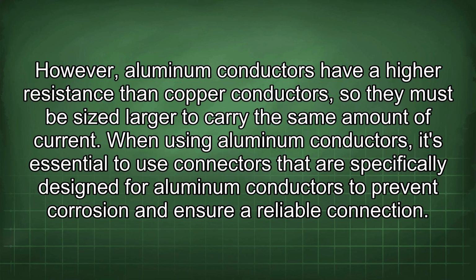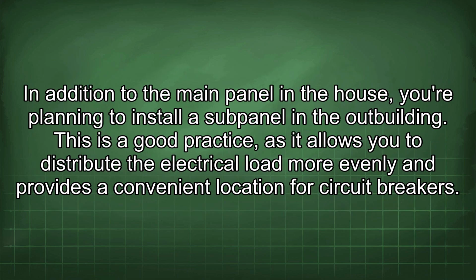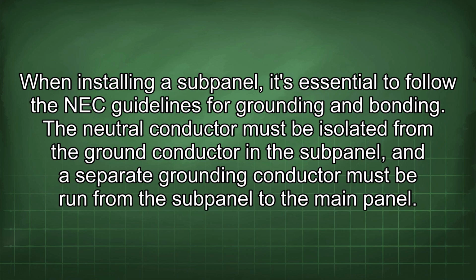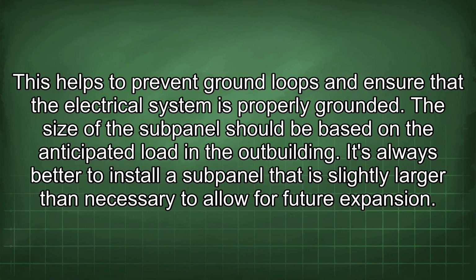In addition to the main panel in the house, you're planning to install a subpanel in the outbuilding. This is a good practice, as it allows you to distribute the electrical load more evenly and provides a convenient location for circuit breakers. When installing a subpanel, it's essential to follow the NEC guidelines for grounding and bonding. The neutral conductor must be isolated from the ground conductor in the subpanel, and a separate grounding conductor must be run from the subpanel to the main panel. This helps to prevent ground loops and ensure that the electrical system is properly grounded.